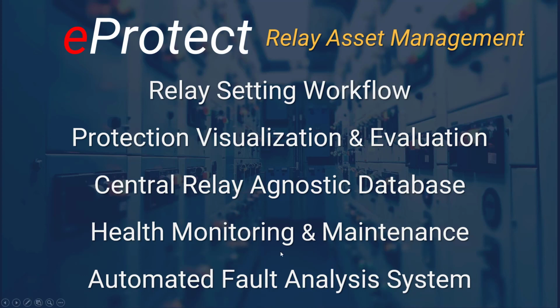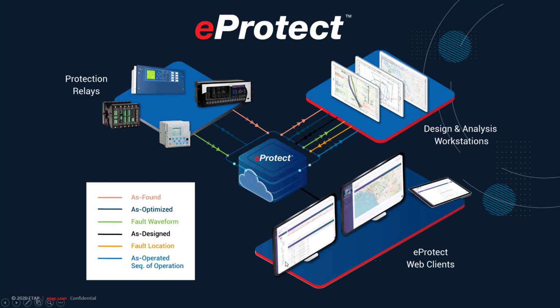It has the capabilities of health monitoring and maintenance, so you can see maintenance schedules. You can see the health of the devices. It also comes with, or is integrated with, the automated fault analysis system. So it collects COMTRADE files, fault files basically, from the system, and then based on that it can actually determine the location of the fault. So it gives you a complete centralized view of all the different protected devices, different brands, in one central location.